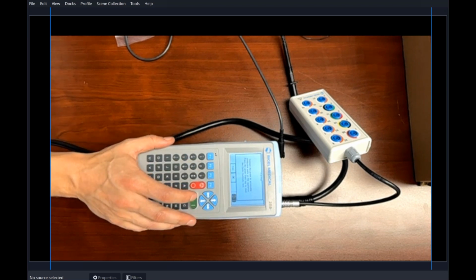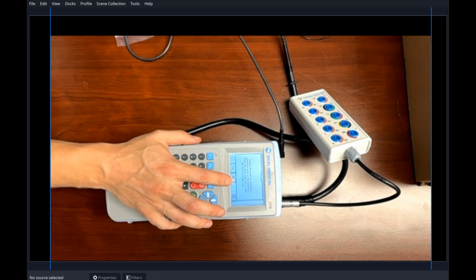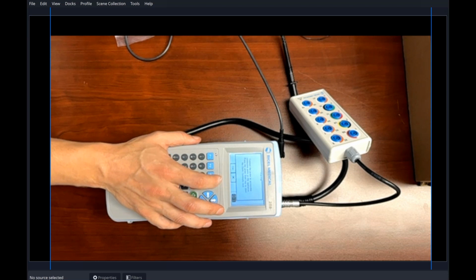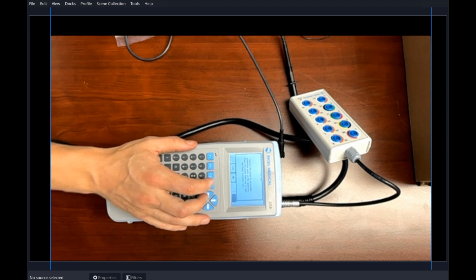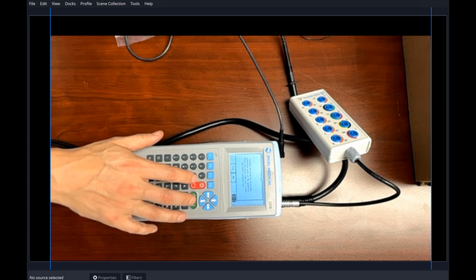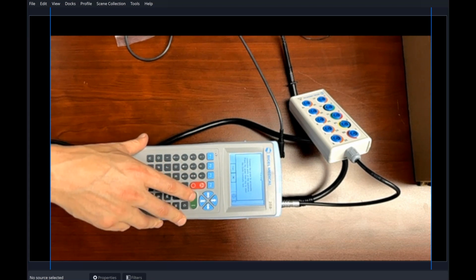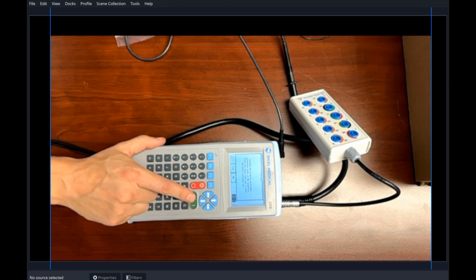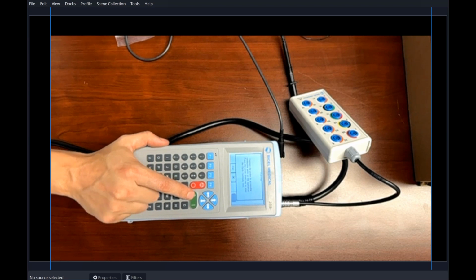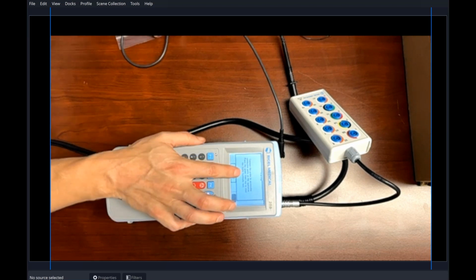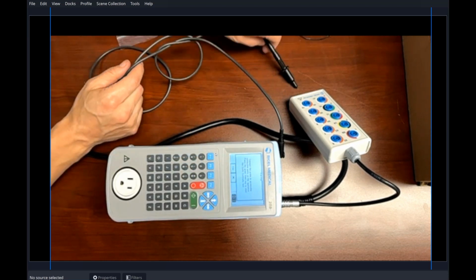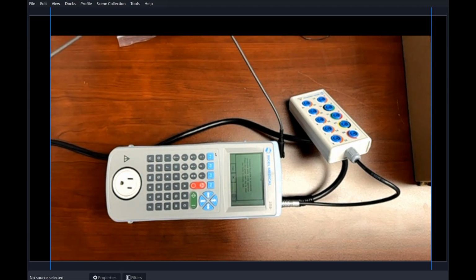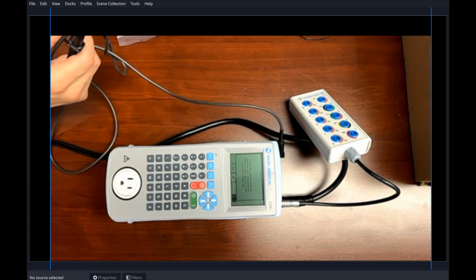So I need to connect the probe to an accessible part. It'll run through ground bond and then touch leakage, patient leakages, and also the patient leakage with the device switched on or off, and any fault conditions that are included. So it's fully automated from here. Once you've keyed in the asset information, you just follow the prompts. It will tell you where the device needs to be connected. So here it's saying connect the probe to accessible conductive parts on the appliance, then press the green start key to start the ground continuity test.